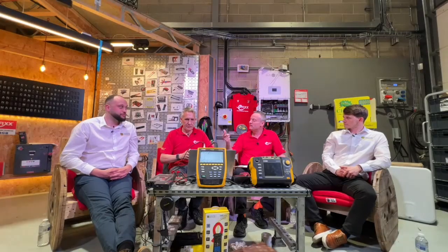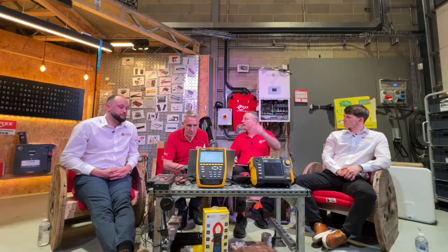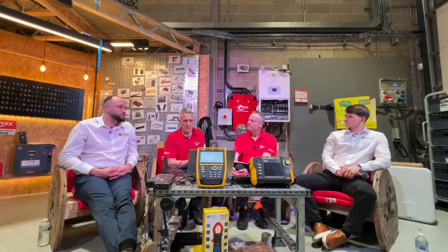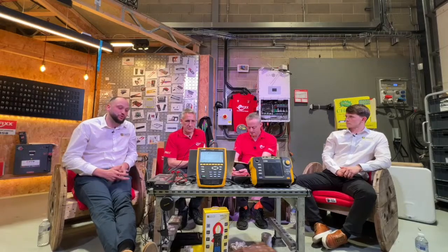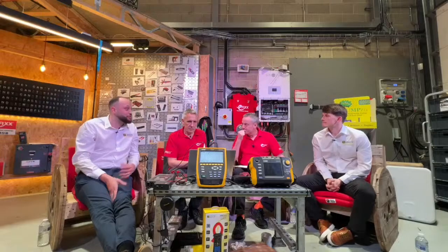So going back through it, what it can do, it can do everything we've just discussed. Three-phase is quite important - if you've got a three-phase installation, you're installing EV chargers. If you're doing single-phase chargers, you'll be looking at which phase was loaded. They weren't equally loaded, and if you're introducing across 3 phases, you need to make sure you've got the headroom. You want to try and balance the load as best as possible - not always possible, but that's the goal. If you set it logging up, you can do load survey plans, pre-install load surveys and various stuff with a 3-phase system.